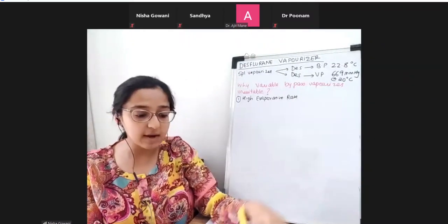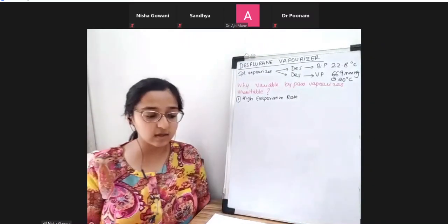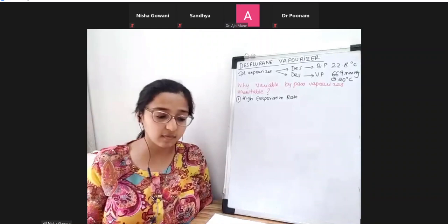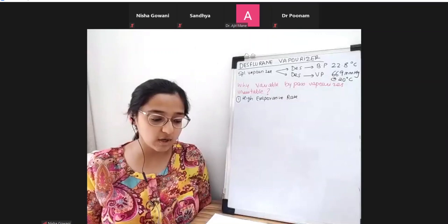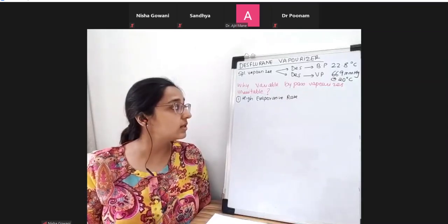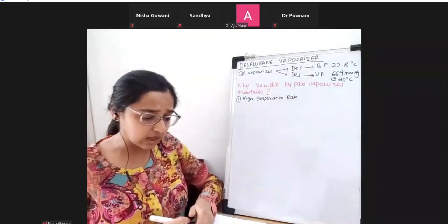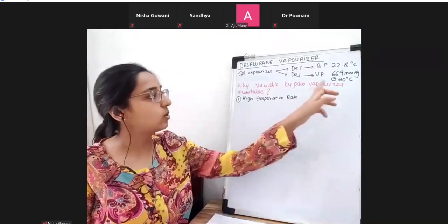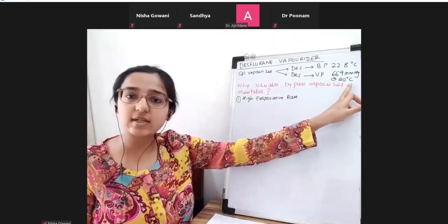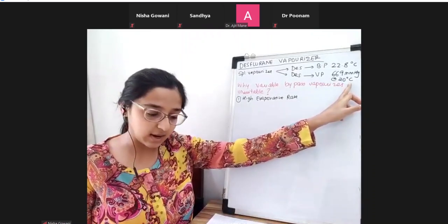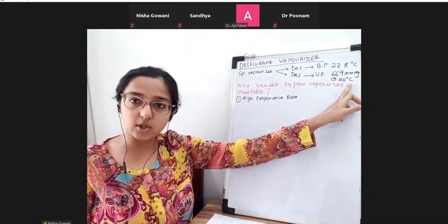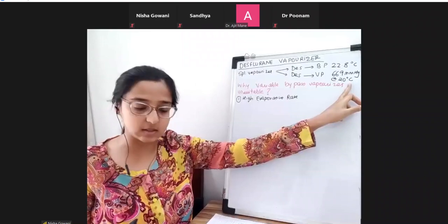Why do we need a specialized vaporizer? So the first reason which I've written is the high evaporative rate. Okay. So at 20 degrees Celsius, we know the vapor pressure is 669, right? And it is almost near to 1 atmosphere, which is the value 760 millimeters mercury.